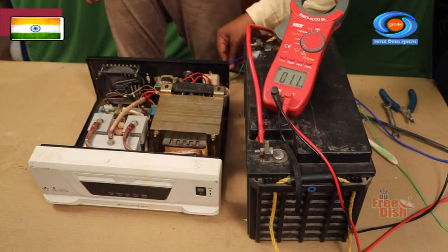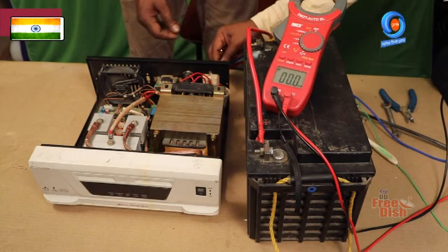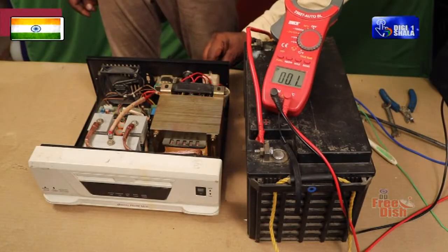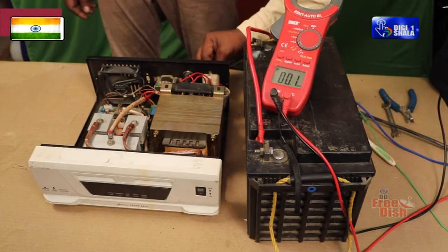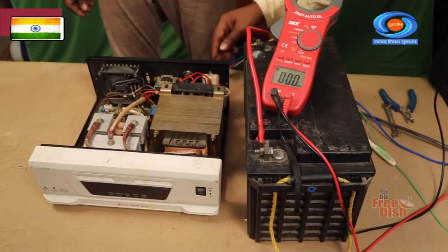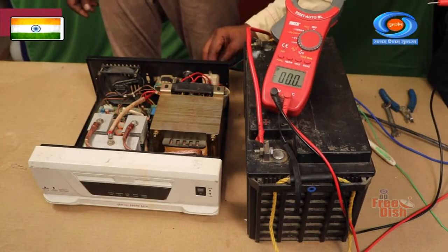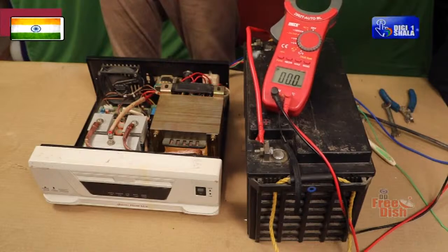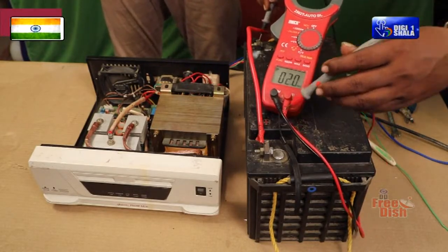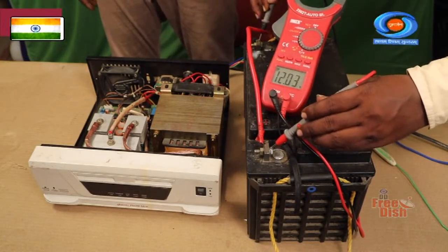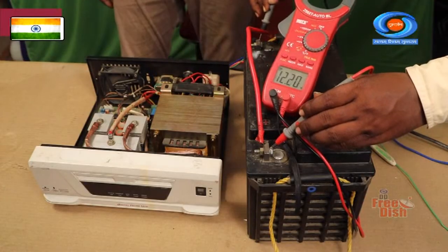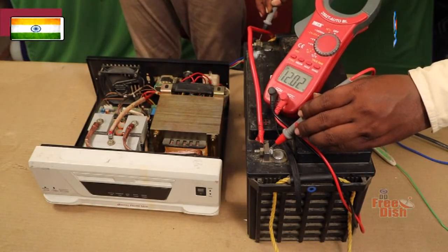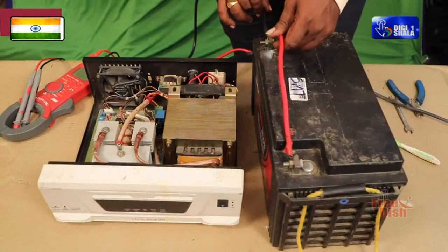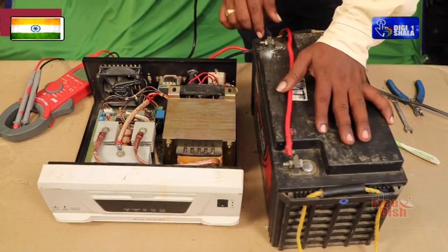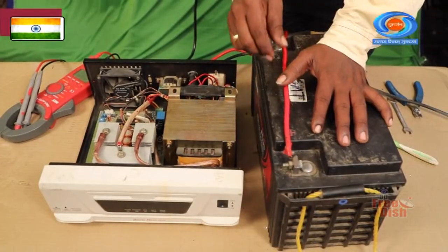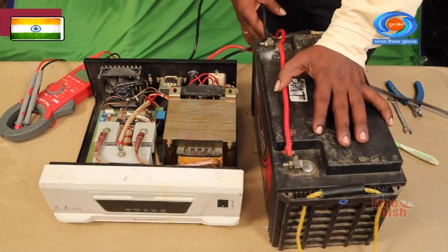Connect the inverter circuit with supply. Disconnect the main AC supply and test the output of the inverter by connecting load and note down the performance. Use a multimeter and an oscilloscope to measure voltages, currents and waveforms. Check the backup time of the inverter and verify the same with the manufacturer's manual. Check for any issues such as excessive heat or abnormal behavior and troubleshoot accordingly.